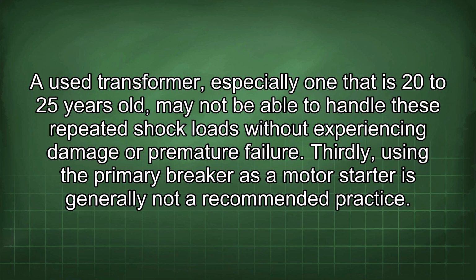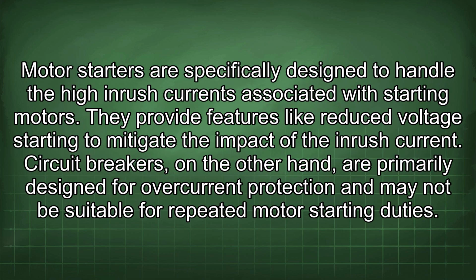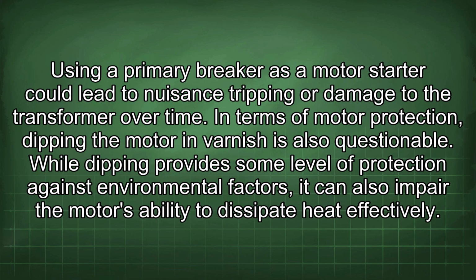Thirdly, using the primary breaker as a motor starter is generally not a recommended practice. Motor starters are specifically designed to handle the high inrush currents associated with starting motors. They provide features like reduced voltage starting to mitigate the impact of the inrush current. Circuit breakers, on the other hand, are primarily designed for overcurrent protection and may not be suitable for repeated motor starting duties. Using a primary breaker as a motor starter could lead to nuisance tripping or damage to the transformer over time.